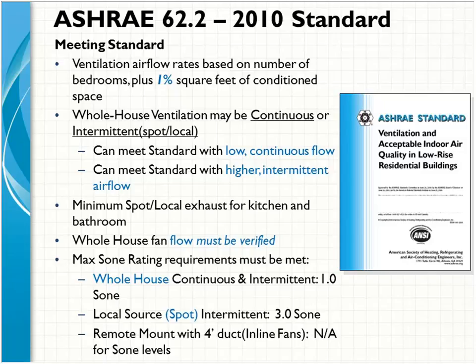So if the home required 50 CFM of continuous ventilation, we could buy a fan and install it and run it at 50 CFM, or we could have a 100 CFM fan running for 30 minutes an hour. And as long as we accomplish the goal at the end of the hour of removing the amount of air required based on the number of bedrooms and the square footage of the home, we've met the code. So there's 2 approaches that we can do to meet that, and the equipment that you install will determine how you want to do that. All right, and then we're going to talk about spot ventilation a little later, so I won't go into that now.